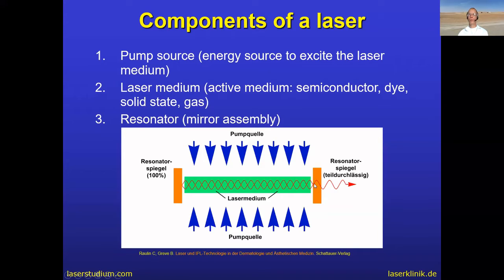If you have two mirrors and look between them, you see yourself many times replicated — this is the same principle here. It's very important that the mirrors are very parallel; even a few millidegrees of distortion will make the laser unusable. So it's very complicated, and you should not bump a laser because the mirrors can be damaged and then the laser will not function anymore.